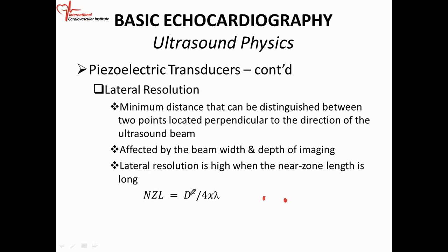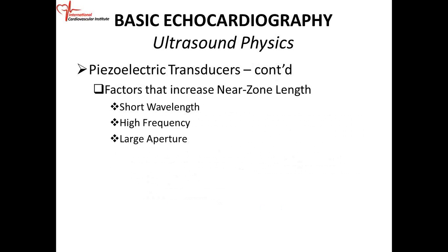And this is the diameter squared divided by 4 times the wavelength of the ultrasound beam. Okay, as opposed to axial resolution, which is spatial pulse length divided by 2. And the lateral resolution is high when the near zone length is long, and that's the diameter of the transducer squared divided by 4 times the wavelength. All right, so that's lateral resolution.